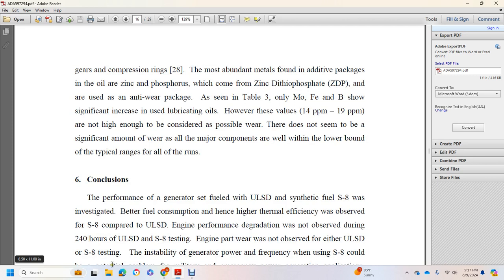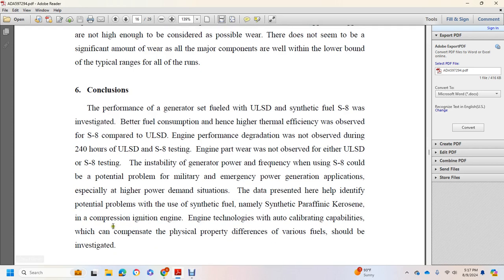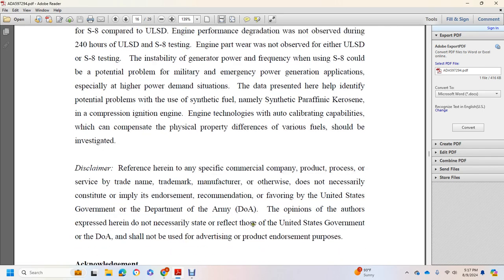6. Conclusion. The performance of the generator set fueled with ultra-low sulfur diesel and synthetic fuel S8 was investigated. Better fuel consumption, hence higher thermal efficiency, was observed with S8 than with ultra-low sulfur diesel. Engine performance degradation was not observed during the 240 hours of ultra-low sulfur diesel and S8 testing. Engine part wear was not observed with either fuel. Instability of the generator power frequency when using S8 could be a potential problem in military emergency power generator applications, especially in high power demand situations. The data presented here help identify the potential problems with using synthetic fuel, namely synthetic paraffinic kerosene, in a compression ignition engine. Engine technologies with auto-calibrating capabilities can compensate for physical property differences. Various fuels should be investigated.